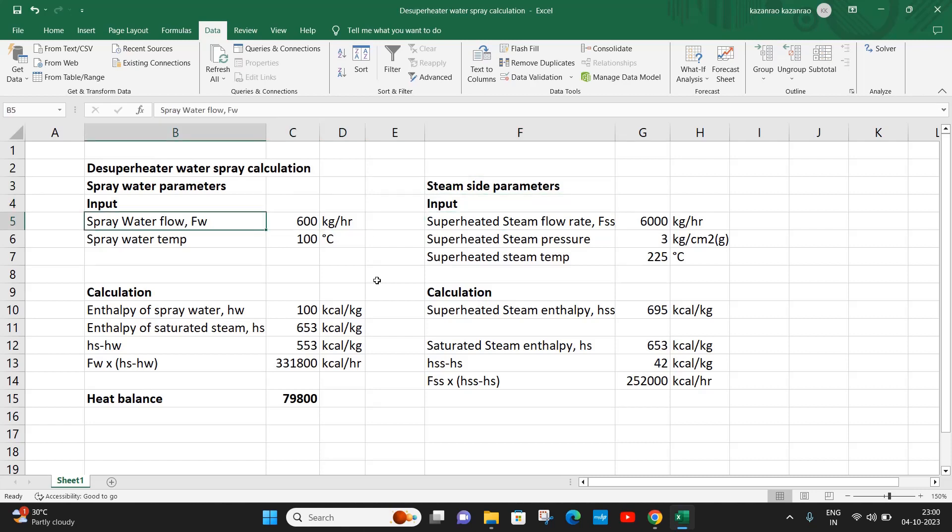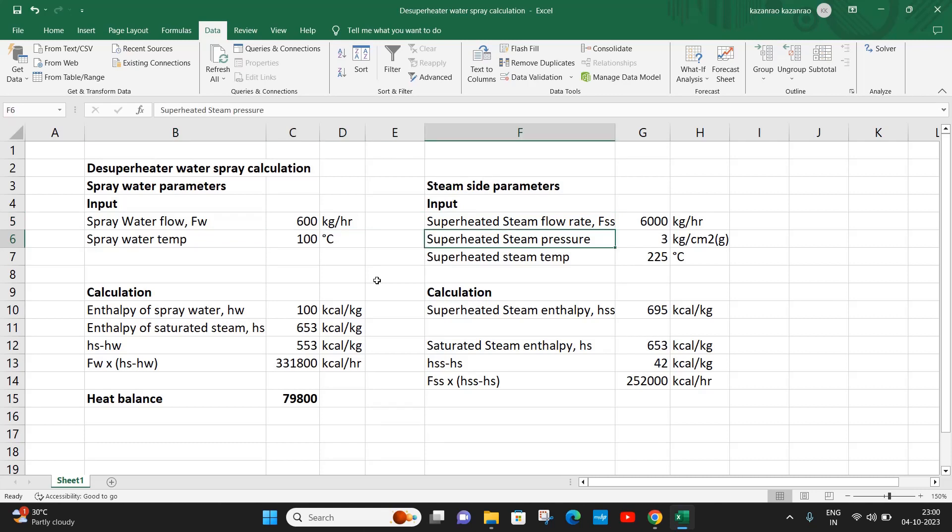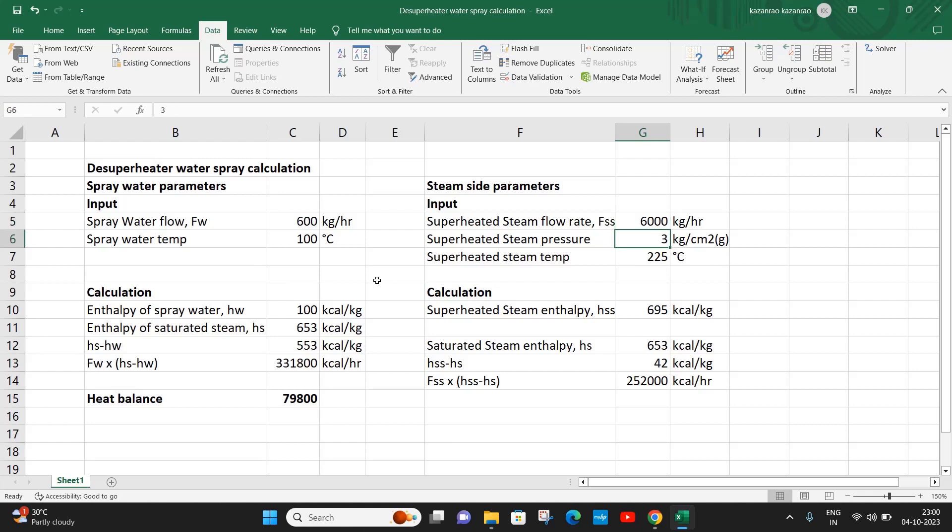Now, the superheated steam flow rate is 6000 kg per hour. This is the steam which is already in superheated condition. Let us assume a pressure of 3 kg per cm squared at a superheated temperature of 225 degrees. For 3 kg pressure and 225 degrees, the enthalpy of this superheated steam is 695 kcal per kg.